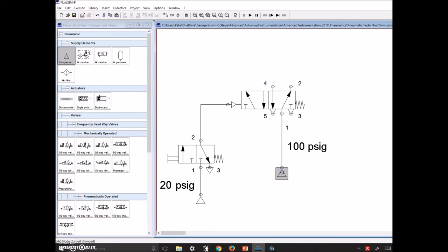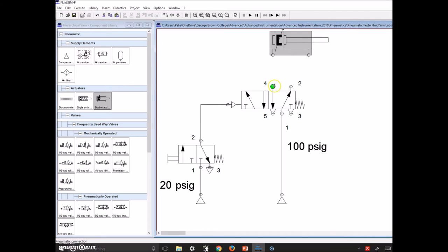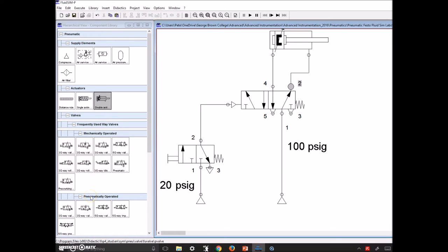So 20 psi is now controlling a 100 psi relay. Then we need a double acting cylinder. I need the air to come up and push this back in the retracted position — that looks good — and a path for that air to exhaust. The only thing this FluidSim is missing is the pneumatic indicators, so when we extend we're going to tee in a green pneumatic indicator, and for the retract we'll tie in a red pneumatic indicator. I think this looks good — let's press play.